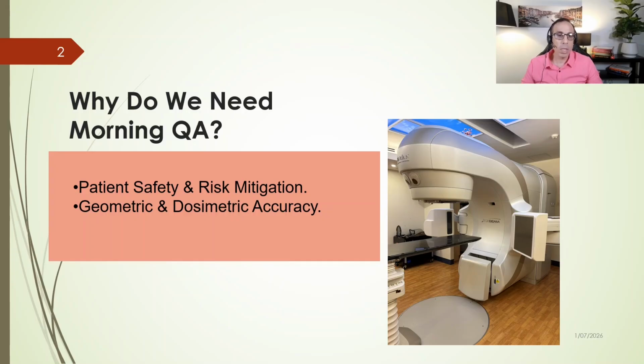The reality is that a Linac is a highly complex machine. It has thousands of electronic, mechanical, and software parts. Honestly, even when the machine looks perfect on the outside, small changes happen. Temperature shifts, electrical shifts, or minor power issues can affect it. Important parts like the MLCs, lasers, and imaging systems can slowly move out of their correct positions.